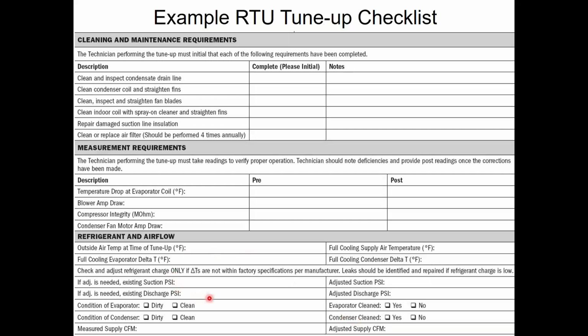The refrigerant things, and there's even a note on here, there's no reason to start putting your gauges on the system. I know the first thing every tech does is put their gauge on the system. There's no reason to put your gauge on the system unless you suspect that something's wrong. So until you've measured the temperatures, there's no reason to put the gauges on. If you measure the temperatures and everything looks good, don't put the gauges on. Because every time you put the gauges on, A, you leak a little bit of refrigerant out on accident just by hooking them up. And B, you could allow a little bit of contaminant to get in. So there's no reason to get into the system if you don't have to.